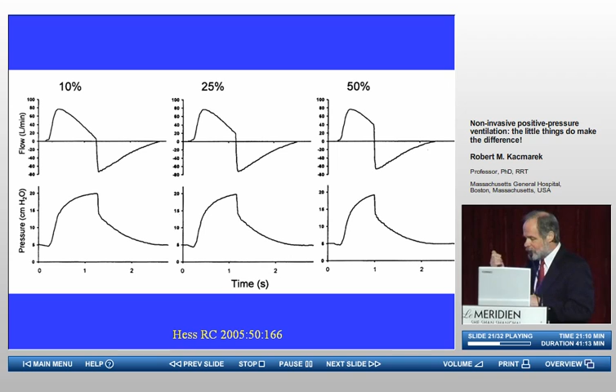Just for completeness, in intubated patients, you can see the opposite phenomenon occurring. In other words, the breath ending too soon, too high a termination criteria, which gives you this appearance of two breaths, one right after the other, on the flow, as well as a secondary bump in pressure here on the airway pressure waveform. In other words, the breath from the ventilator's perspective ended here, but the patient kept inhaling, and they actually went into the expiratory phase at this point in time.